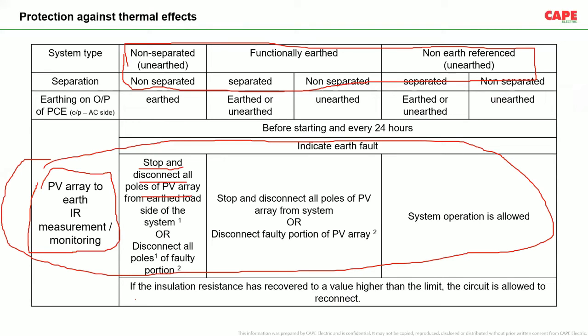So on the earthed side of the load, either you can disconnect the earthing, or you can disconnect the load, or you can disconnect the part of the PV which has created the fault, provided you have a monitoring system for each and every circuit. So that part of the circuit, either you can disconnect, or you can disconnect the functional earthing. As a result, safety is achieved. This is one method, insulation resistance monitoring.